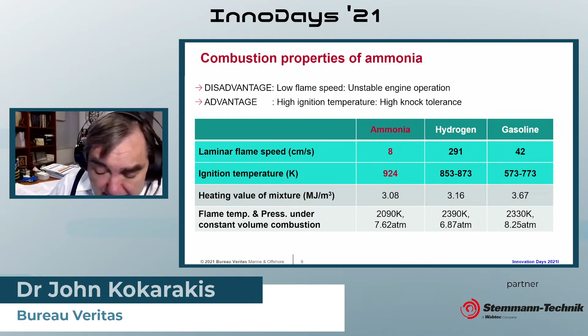Inevitably, we have NOx, the typical problem in our exhaust gases, which needs to be abated because nitrogen is a component of the fuel. Formation of nitrous oxide, which is also known as laughing gas, may be possible, and this is a problem because it is 300 times worse in global warming potential compared to carbon dioxide. We need to provide, first of all, SCR, selective catalytic reactors, or exhaust gas recirculation for the abatement of NOx, or even scrubbers that will withhold the laughing gas.